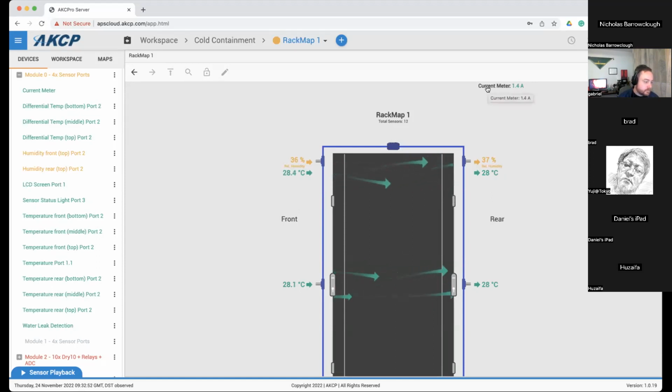but it's enough for the sensorCFD to have an idea as to the power of this rack. So the thermal map sensor comes with the current meter, and you plug that into a single sensor port on the SPX. Then when you drag and drop that across onto the rack, you'll see everything just gets positioned exactly where it needs to be. So these animated arrows are showing the delta T values. So you can set the thresholds just like...